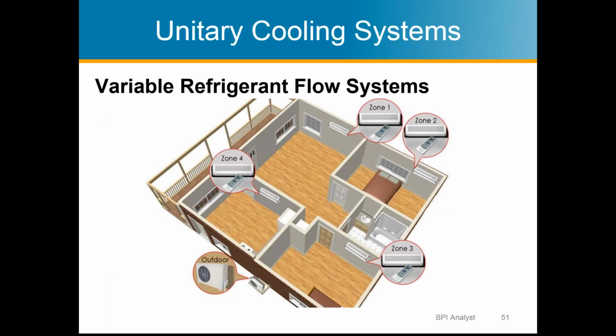A lot of variable refrigerant flow systems or ductless mini splits would be set up in a manner similar to this. So you'd have one outdoor system, and here you've got 4 different zones, and each zone is its own head. So there's no ducts, but you would have a small fan in each one of these head units that's cooling each room just the amount of cooling that each room needs, instead of having all the rooms turn on at the same time. Maybe zone 1 and 2 is on the west side, and it's going to need more cooling than zone 3 and 4. So it's able to adjust according to the needs of each room.